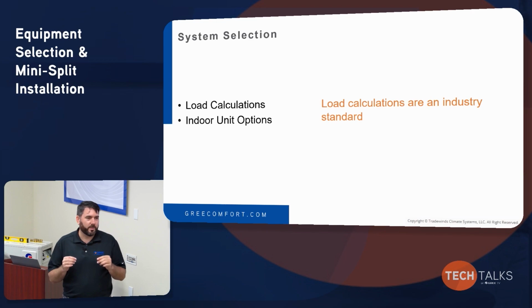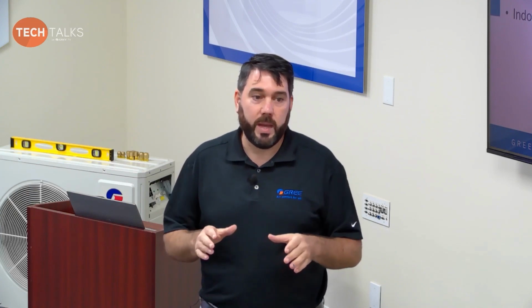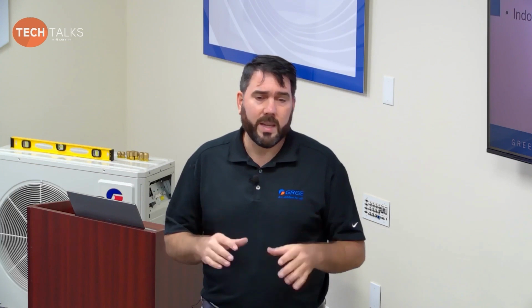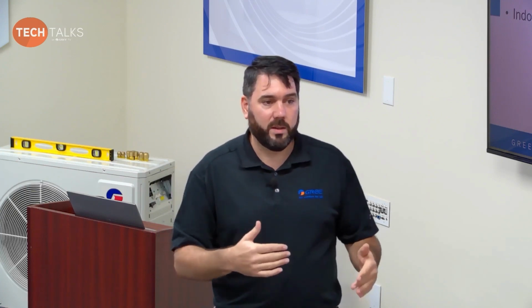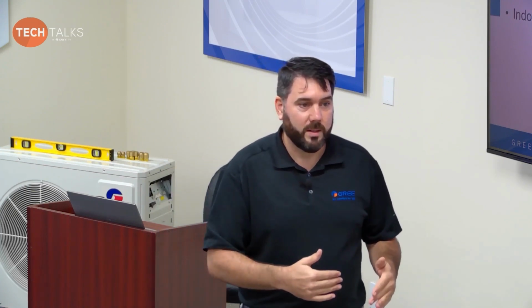In the past there's been this terrible phrase about inverters and mini splits, that you can't oversize them. That is completely false. You can oversize them, and very easily, especially with the ultra heat products, because they can heat down to -31. If you have another manufacturer already plugged into your load calculation software and you accidentally use that when you get to your Manual S for your equipment selection, you're going to way oversize the equipment, because at 0 degrees, a 3-ton Gree unit may be putting out 100% of its capacity, whereas another brand may only be putting out 80%.